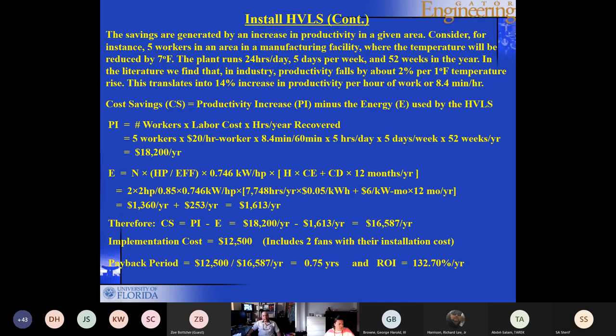Here we got the E, which is the cost of energy. The energy first. Let's compute the amount of energy. There are 2 fans, so 2 times 2 horsepower fans. The efficiency of the fan is 85%. You convert it into kilowatts by multiplying by 0.746, and then you multiply that by the number of hours per year times the cost of energy, plus the demand savings, or the demand that would be associated with this kilowatt, which is going to be multiplied by $6 per kilowatt times 12 months. You end up with the 1360 plus the 253, which gives you 1613.